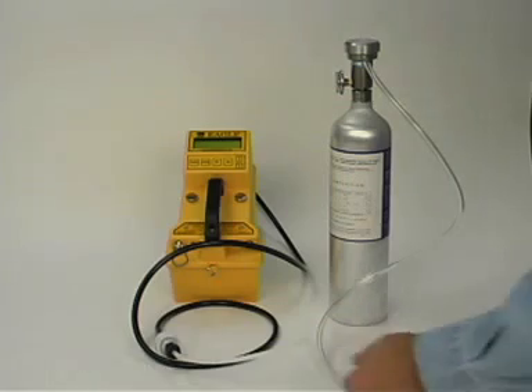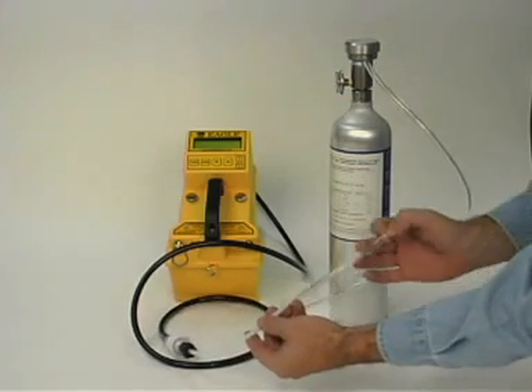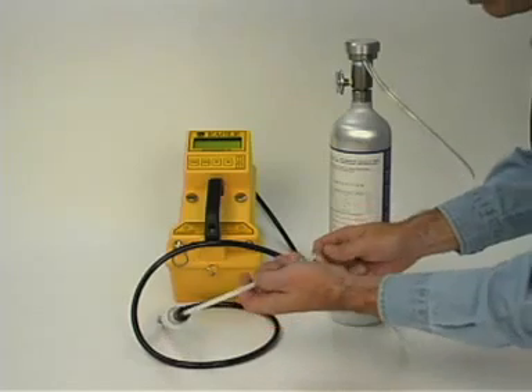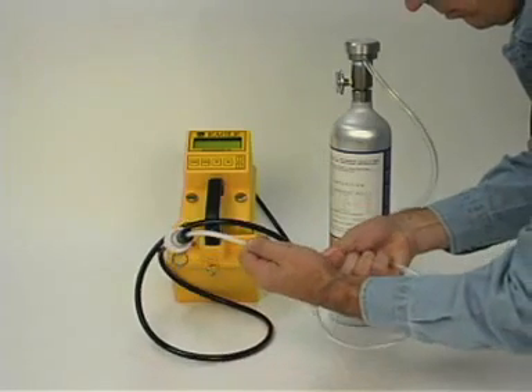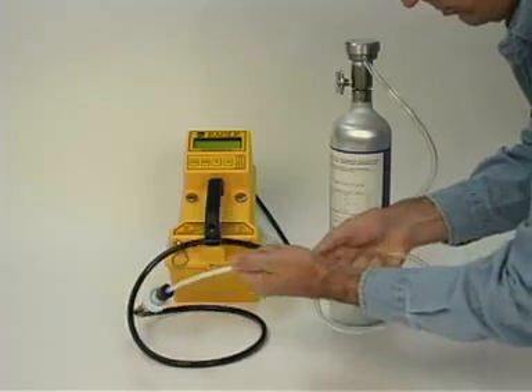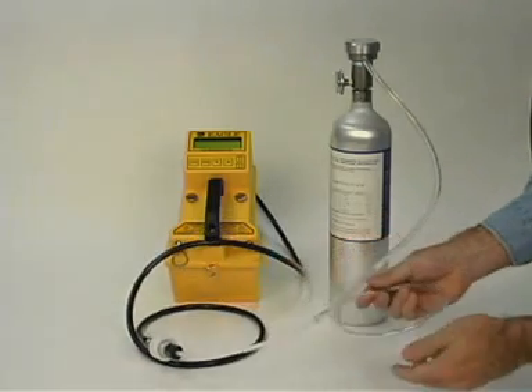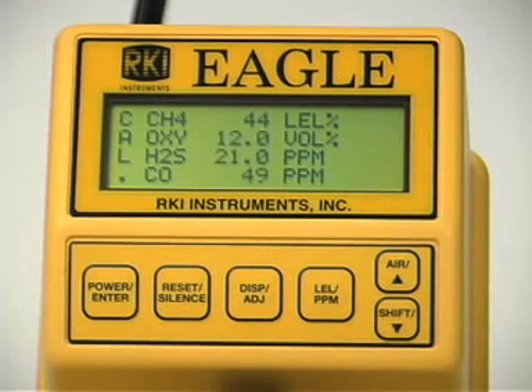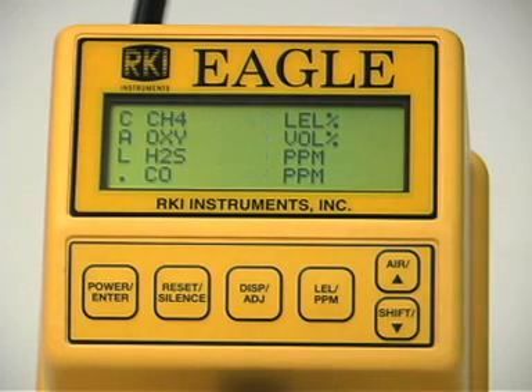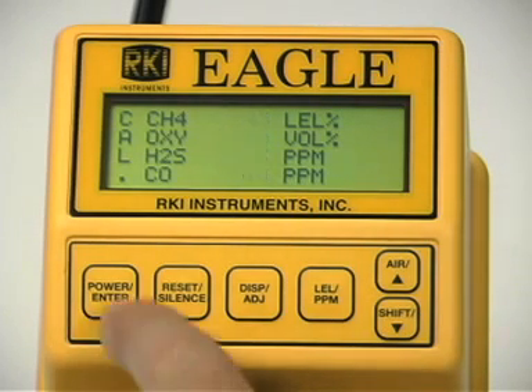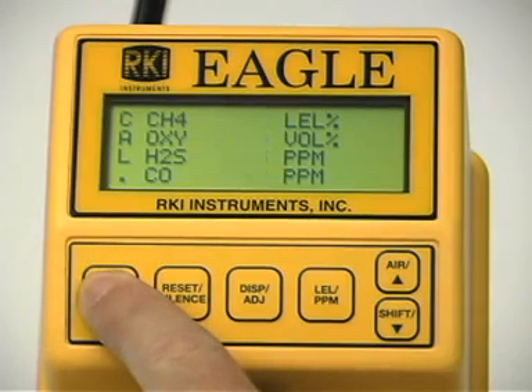Now connect the tubing from the regulator to the Eagle's probe and wait approximately 1 minute or until the readings stabilize. Once the readings have stabilized, press the enter button to set the calibration to the program values. If your calibration was successful, the message Auto Calibration End displays, followed by the calibration menu.